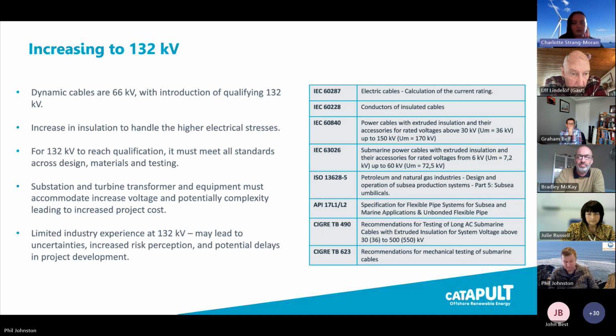Some considerations for 132 kV are listed here - some positive, some areas for us to develop. There's an increase in insulation when dealing with higher voltage cable, to handle the higher electrical stresses, so the cable will be bigger. To reach qualification, it needs to meet all the standards across design, materials, and testing, and we need relevant standards tailored to the expectations of 132 kV dynamic cable.